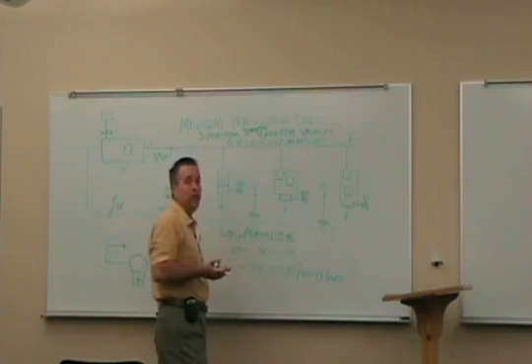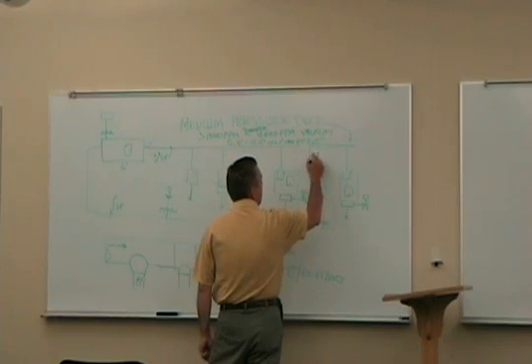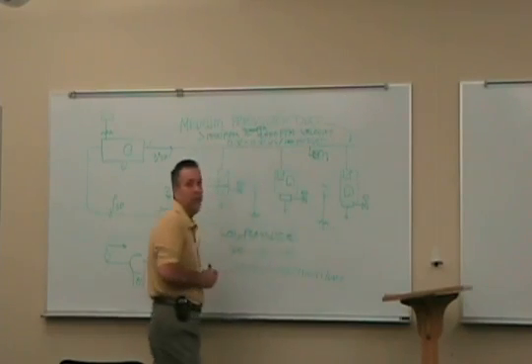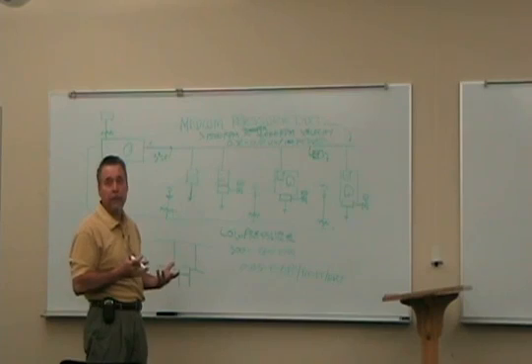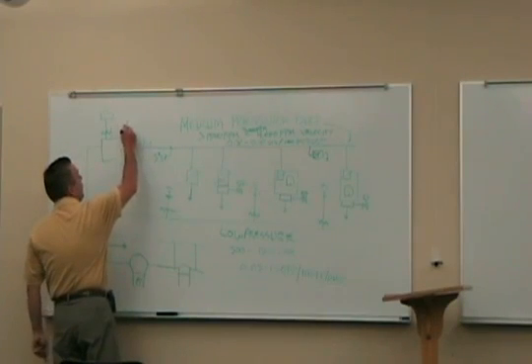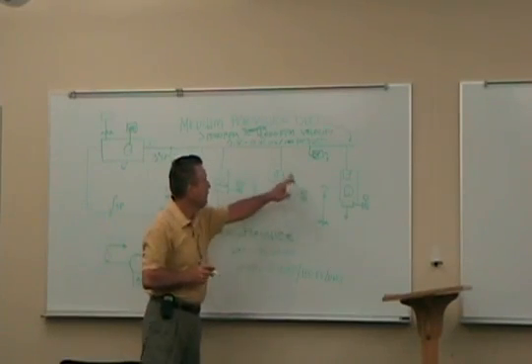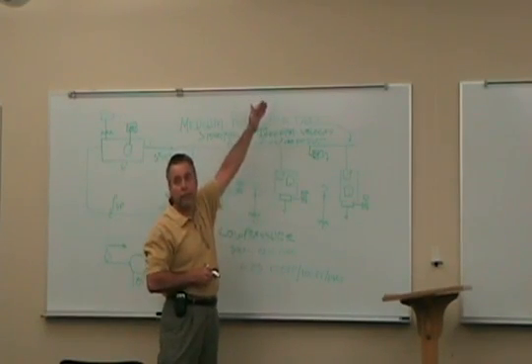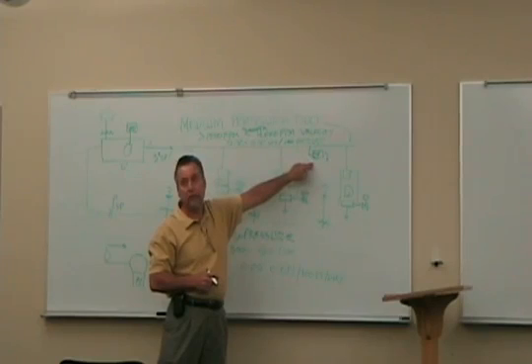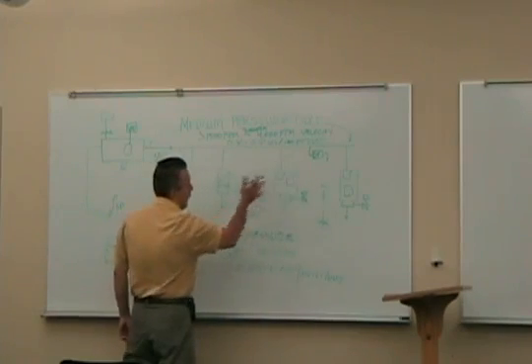this is the only box open. If you remember when we talked about variable volume piping systems, we had a differential pressure transmitter. That references back to just the open space. So we're measuring the pressure in this duct, just like we're measuring the pressure in the piping system. This differential pressure transmitter is talking back to this VFD, this variable frequency drive. So as these shut down, this differential pressure goes up, the fan responds, the airflow goes back down, and pressure goes back down to the set point of whatever the differential pressure is. So that's how the supply duct is balanced.